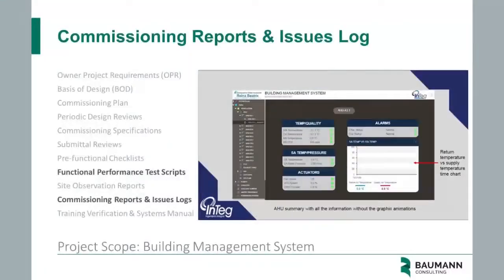And finally, we evaluated the trending capabilities of the BMS to track any operational patterns and alarms generated if required. So we can track the supply temperature against return temperature, for instance, to check against room conditions. We can check zone temperature against supply temperature.